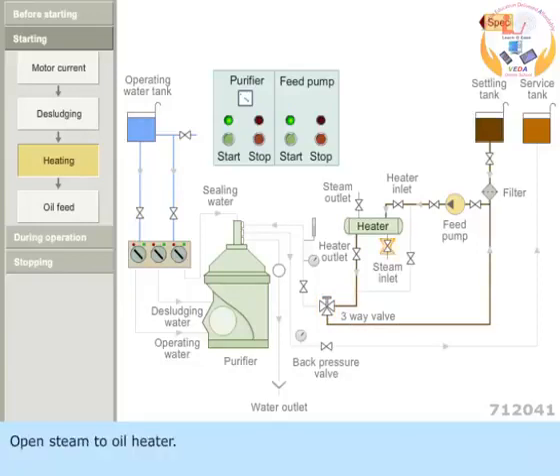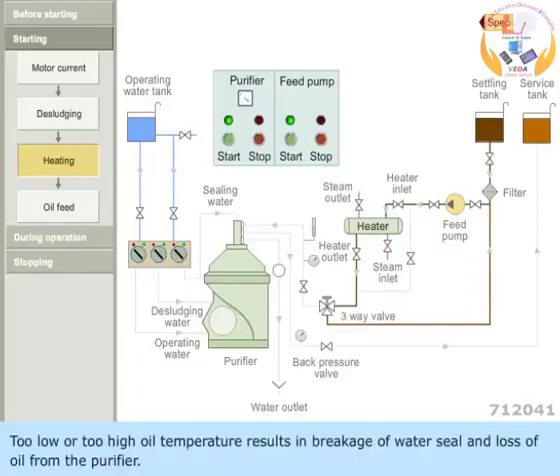Open steam to oil heater. Too low or too high oil temperature results in breakage of water seal and loss of oil from the purifier.